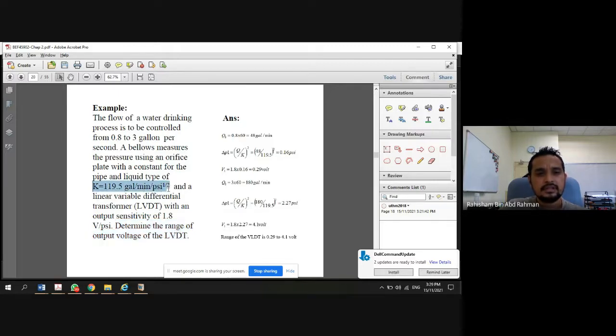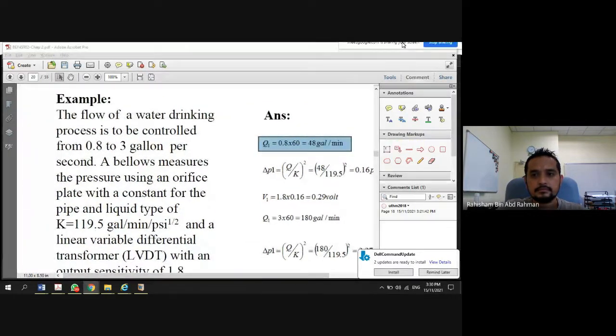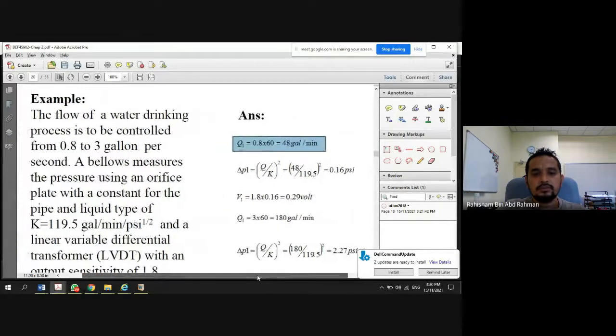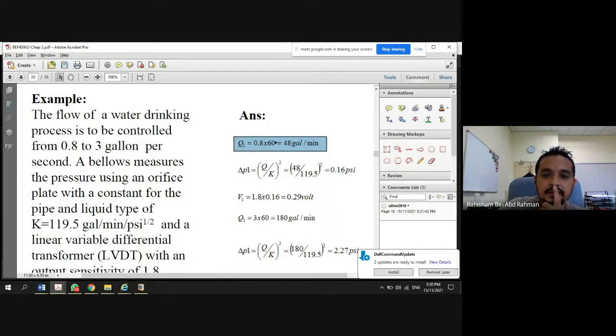Okay, bear in mind this one needs to be translated first, and we are using gallon per second. If you can see here, the parameter given is 0.8 gallon per second, while the constant is given in gallon per minute. So what you have to do first is obtain the flow Q. Q1 is equal to 0.8 gallon times 60. Why 60? Because the value given here is per minute, so we want to have the values in terms of minutes. So we need to multiply by 60, and that will give us 48 gallon per minute. This is the first step.